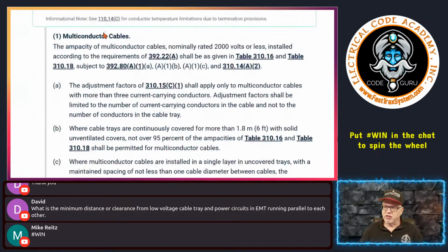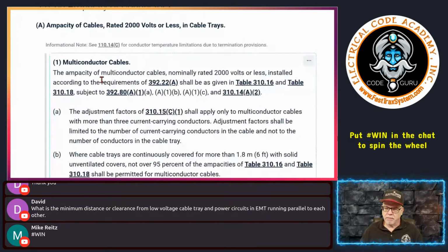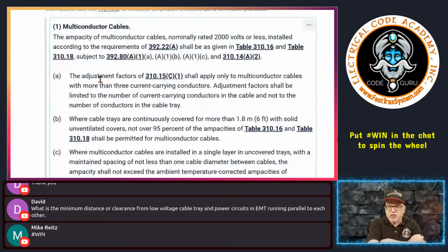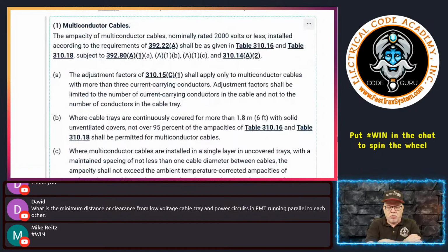It's saying that you do have some applications with multi-conductor cables where you'll have those higher temperature values for the insulation, okay? But for the most part, and what I find the most for engineers, design professionals, and exam prep folks, one of the key takeaways is that you're really going to be doing everything from Table 310.16 ampacity for these cables, okay? So now let's get down to some of the nuances here.